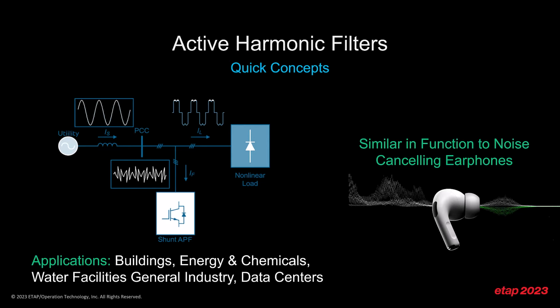It increases the carbon footprint and also increases the chances of non-compliance with utility regulations. And there are also costs incurred due to extra kilowatt hour losses in typical network components such as transformers, cables, motors, and these losses are cascaded back to the utility power plants, resulting in increased CO2 emissions in general. Active filters are a good answer to these tough power quality problems caused by harmonics, load unbalance, and reactive power demand. Active filters can be applied to small, medium, or large applications such as buildings, energy, chemicals, water facilities, general industry, data centers, and they provide harmonic mitigation, load balancing, and stepless reactive power control for inductive and capacitive loads.